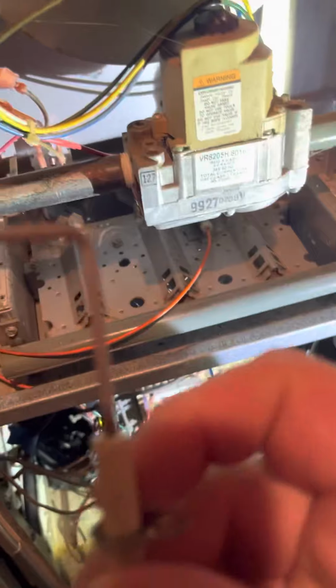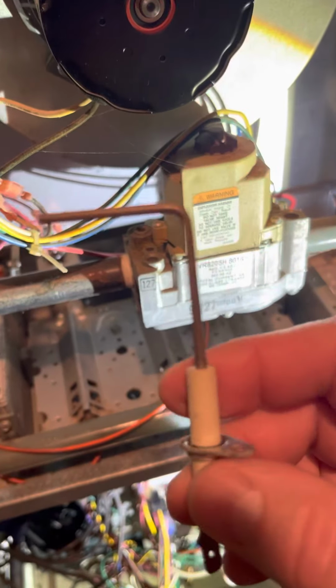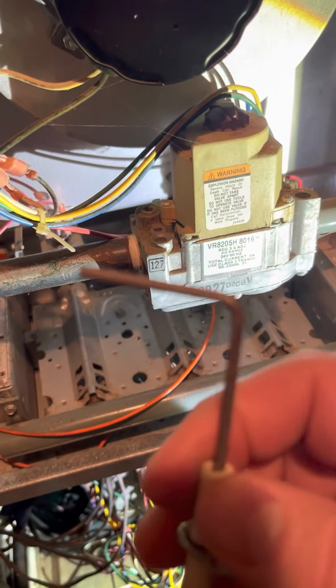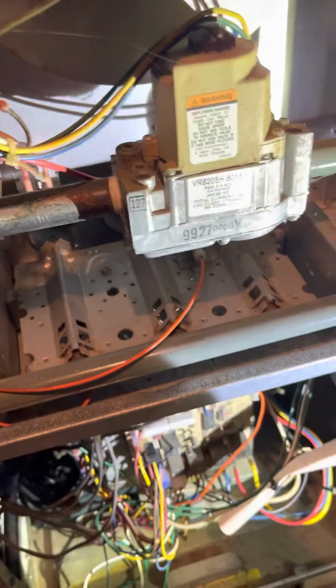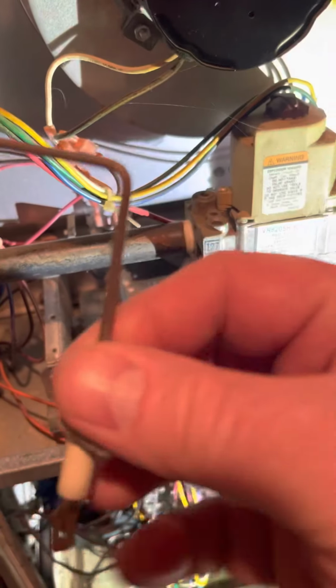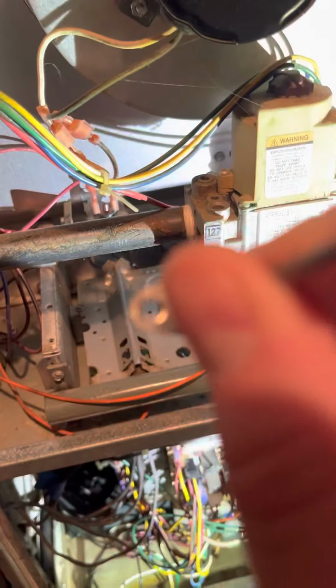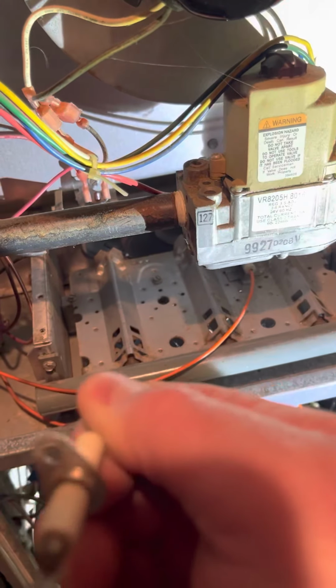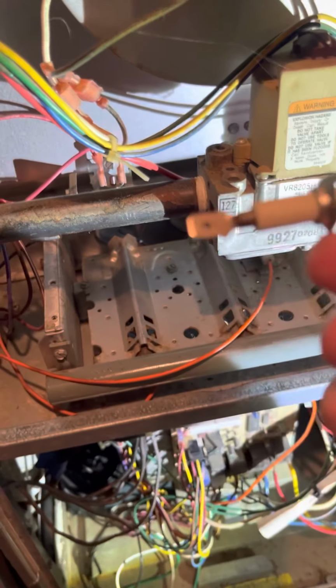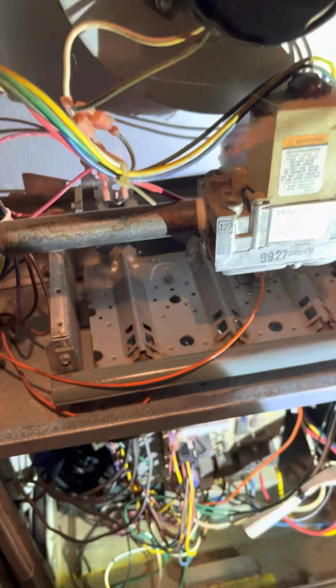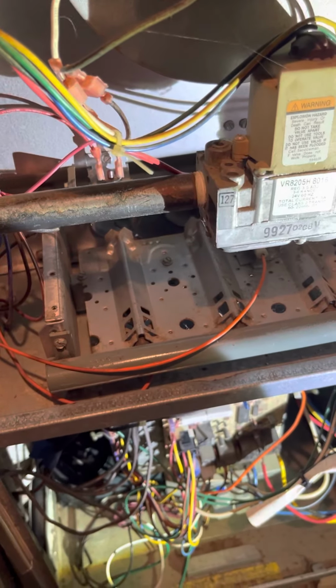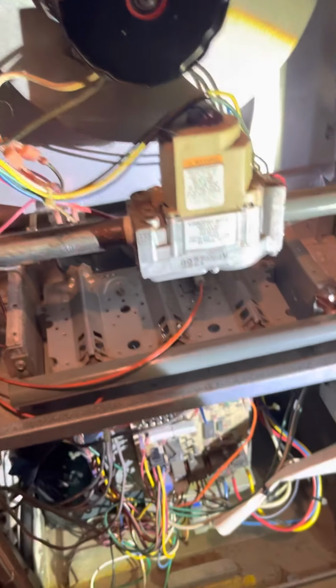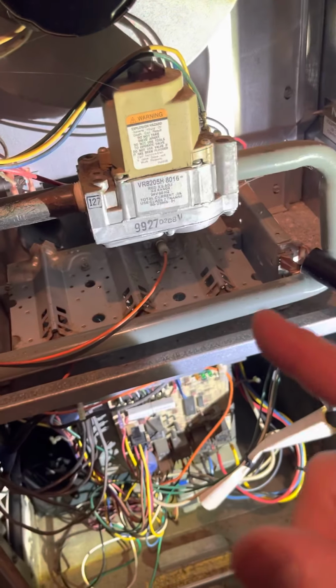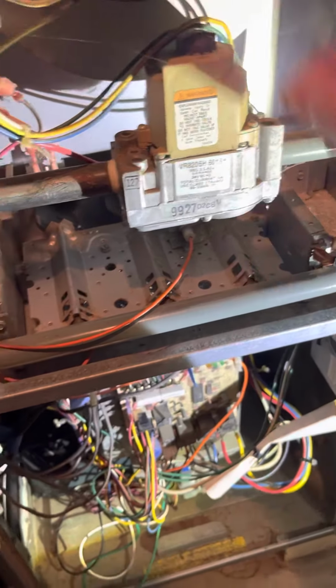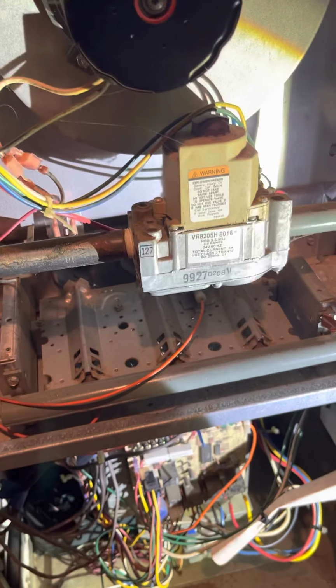Here you can see one that's not installed. The rod should be firm in the porcelain. It should be clean. Even where your ground screw goes in, it should be clean, and your terminal needs to be clean. And you can clean your flame sensor with real fine steel wool. There's all kinds of debate about that. We won't get into that today, but now you see it's going on retry. My furnace retried, and it's going to retry one more time.